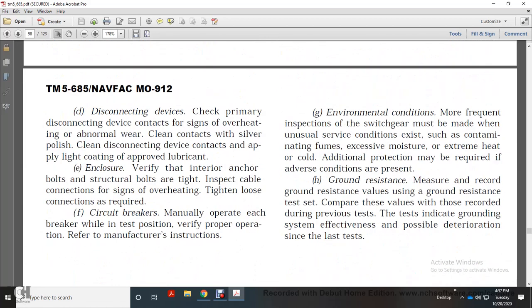Disconnect device: check the disconnect device contacts for overheating and abnormal wear; clean contacts, polish, and apply a light coating of approved lubricant. Enclosure: verify interior, arc bolts, anchor bolts, and structural bolts are tight. Inspect cable connections for signs of overheating; tighten loose connections as required. Circuit breakers: manually operate each breaker in the test position. Verify proper operation per the manufacturer's instruction.